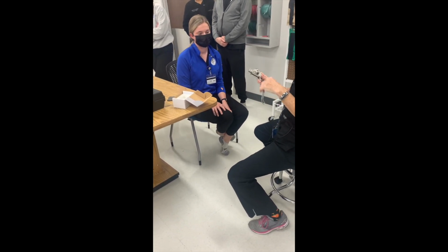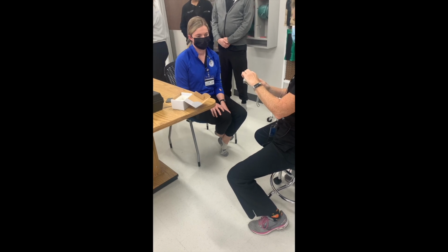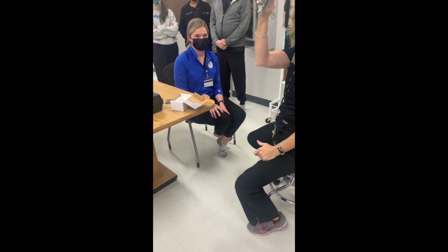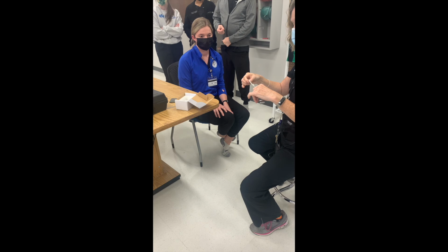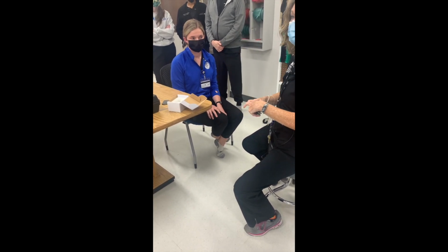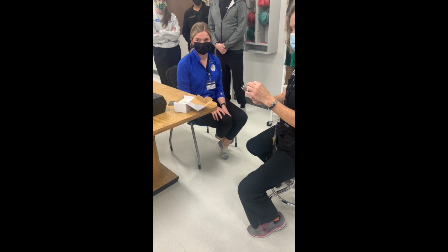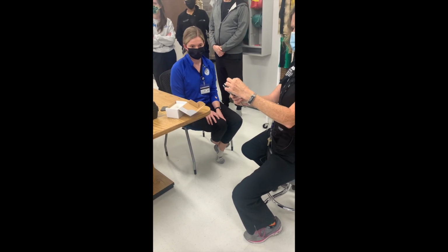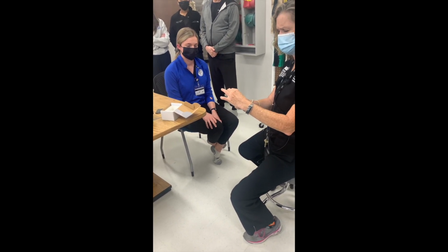This is what we call a pinch meter. Okay? When you use the pinch meter, this goes around your wrist, so if you happen to drop it, it stays in your hand, not on the floor, so to speak. Okay, let me get it zeroed.